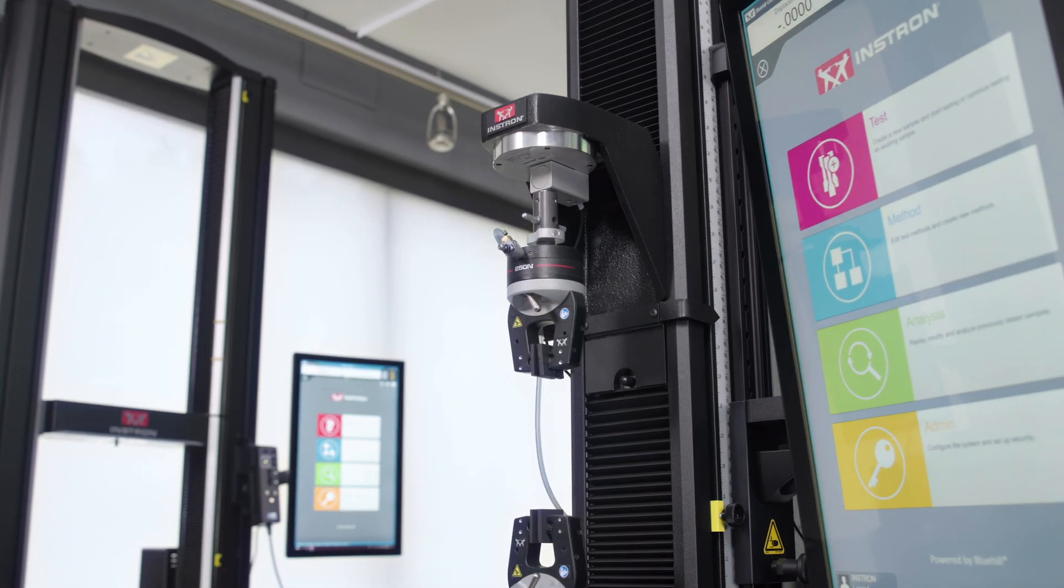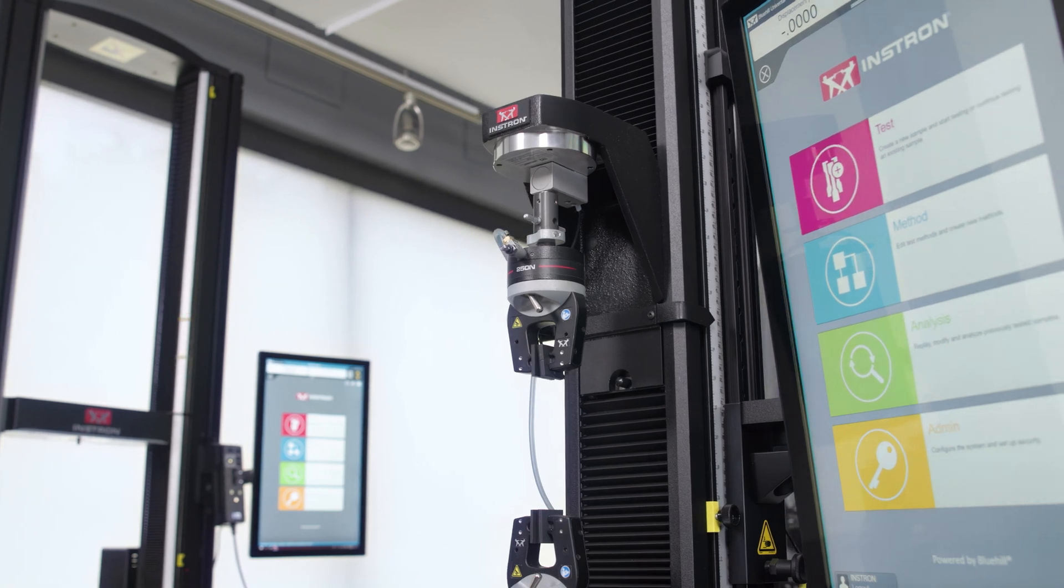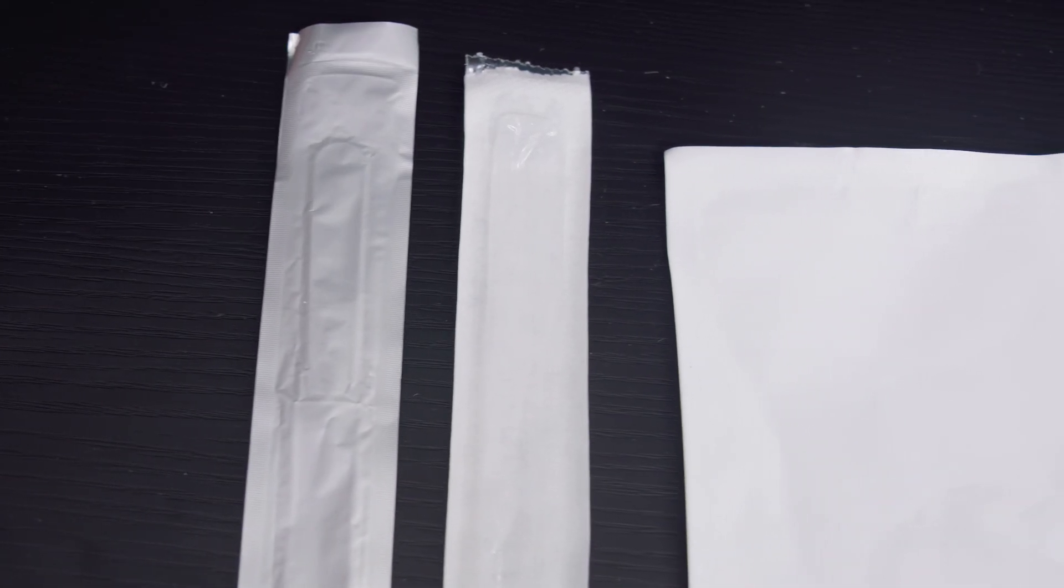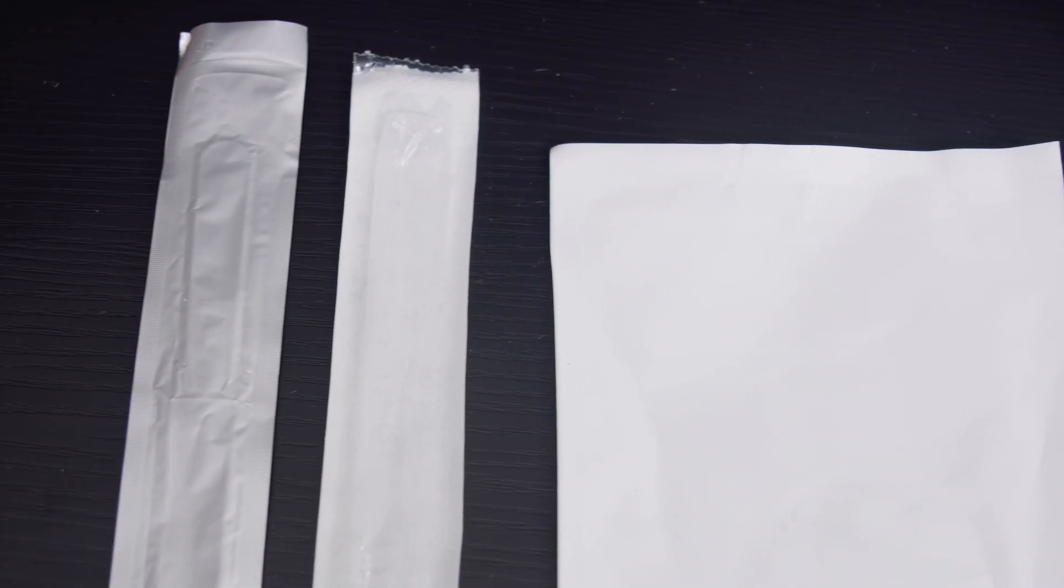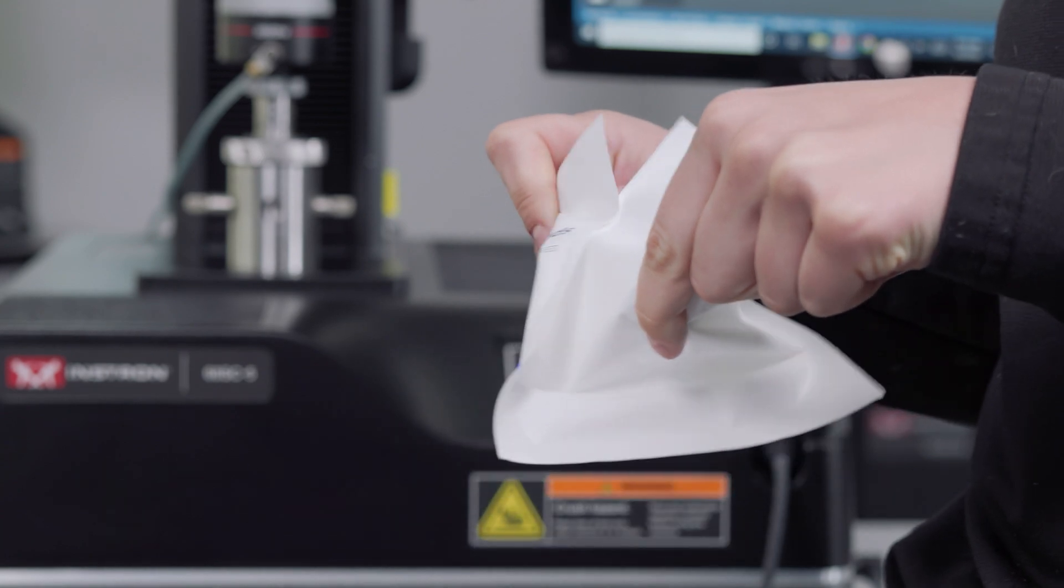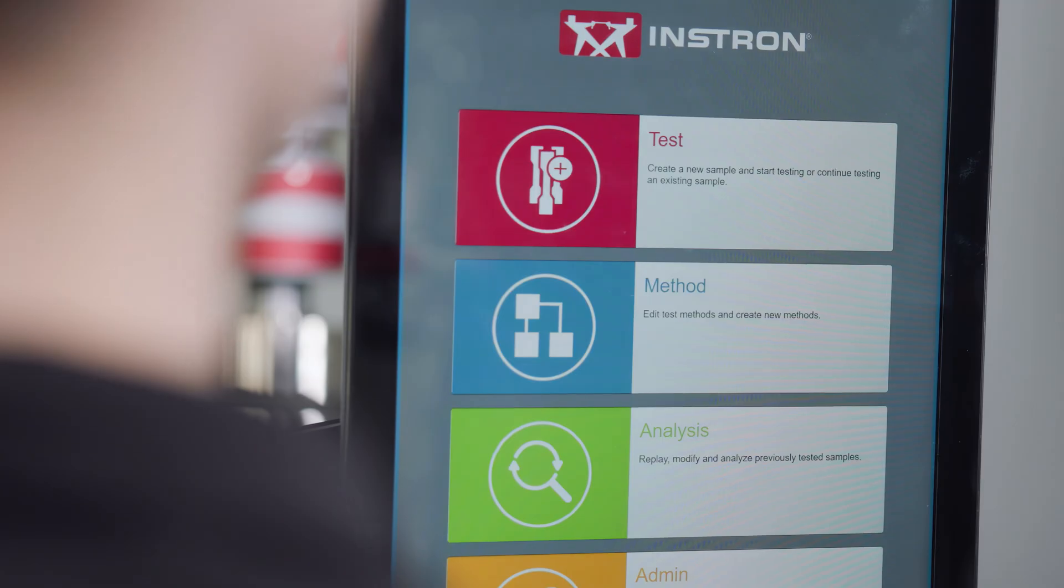ASTM F88 is a testing standard used to determine the seal strength of flexible barrier materials and is used to test the seal strength of packaging.